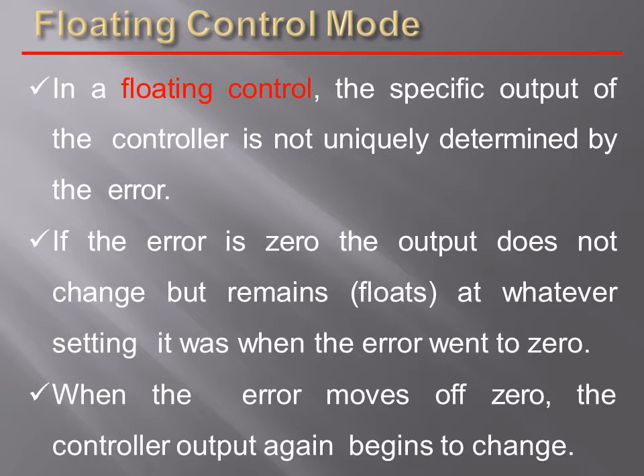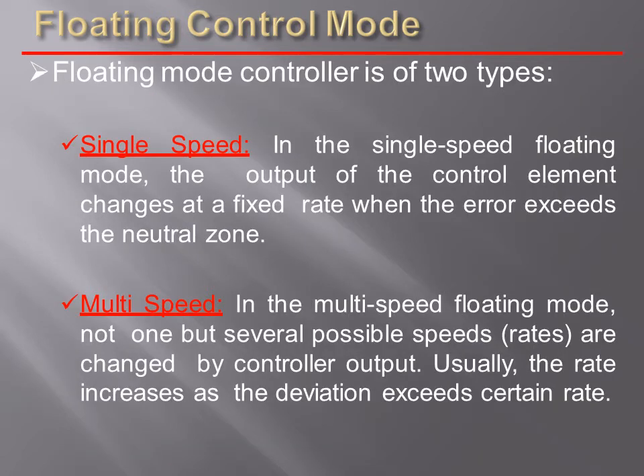There is another type of control mode called floating control mode. In floating control, the specific output of the controller is not uniquely determined by the error. If the error is 0, the output does not change but remains or floats at whatever setting it was when the error went to 0. When the error moves off 0, the controller output again begins to change. The floating mode controller is of two types: single speed and multi-speed.